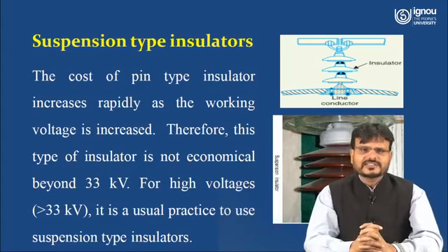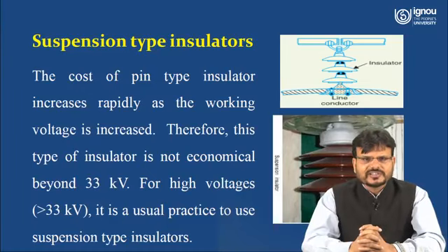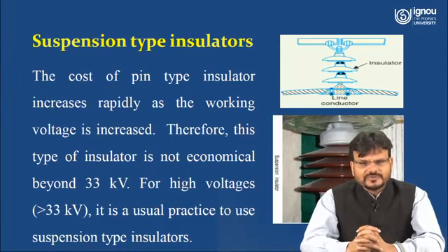The second insulator is called the suspension type insulator. The cost of the pin type insulator increases rapidly as the working voltage is increased. Therefore, this type of insulator is not economical beyond 33 kV. So for high voltage, that is more than 33 kV, it is usual practice to use the suspension type insulator.